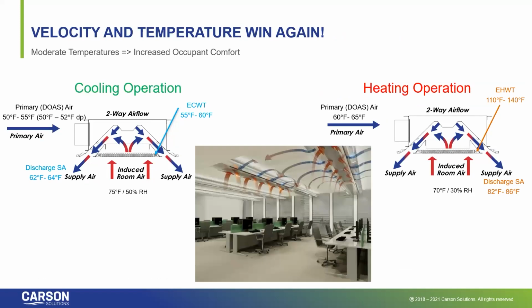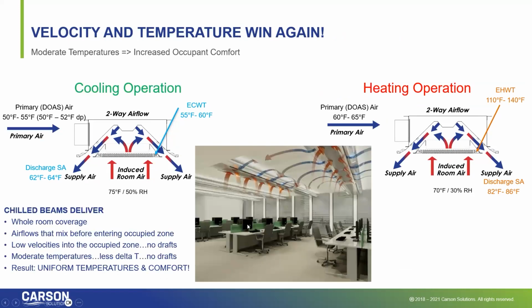Compare that with a chill beam arrangement. You've got a much more moderate temperature being delivered out of the diffuser, and you have entire space coverage of diffusers. And then when you look at proper chill beam design, you look at the slow velocity coming into the occupied space, again, with the total goal of unified temperature and airflow distribution for better comfort.